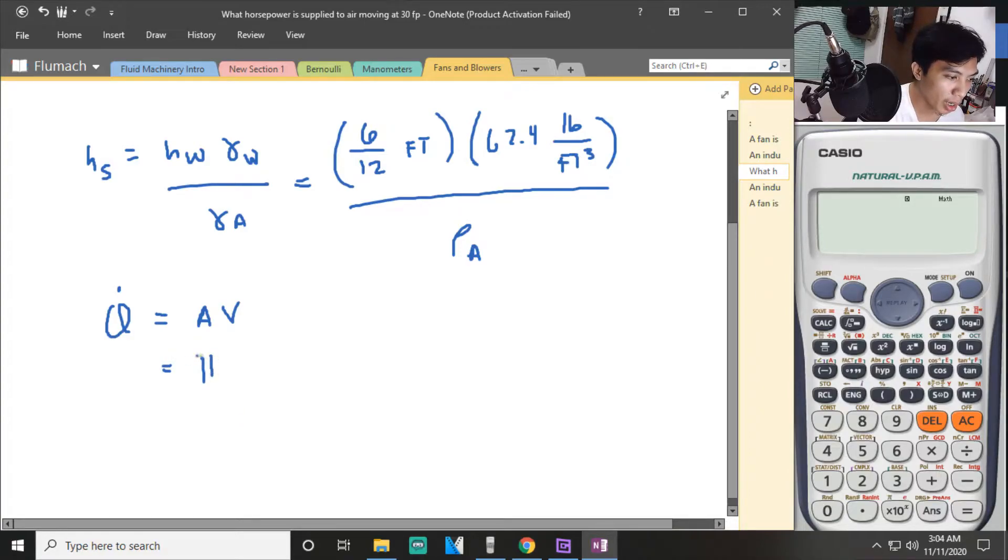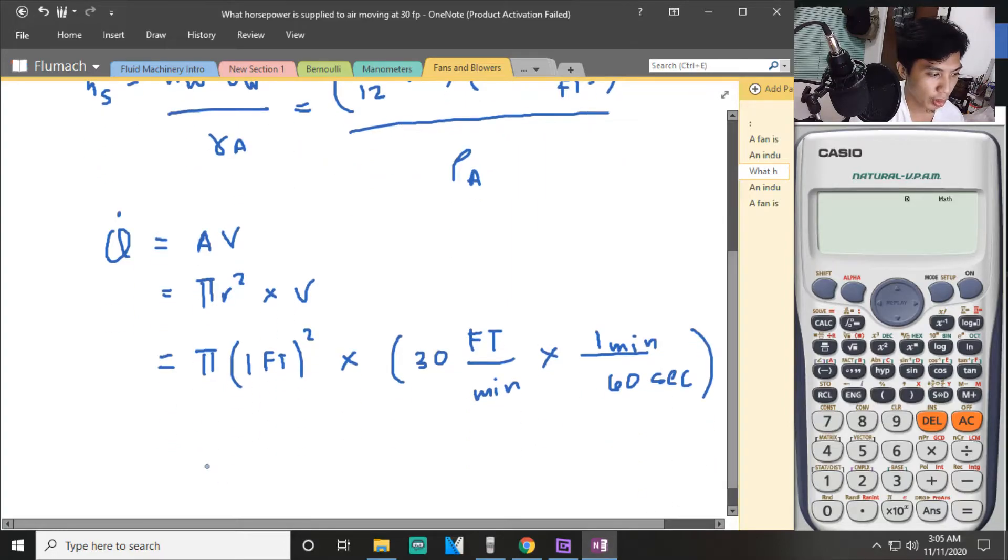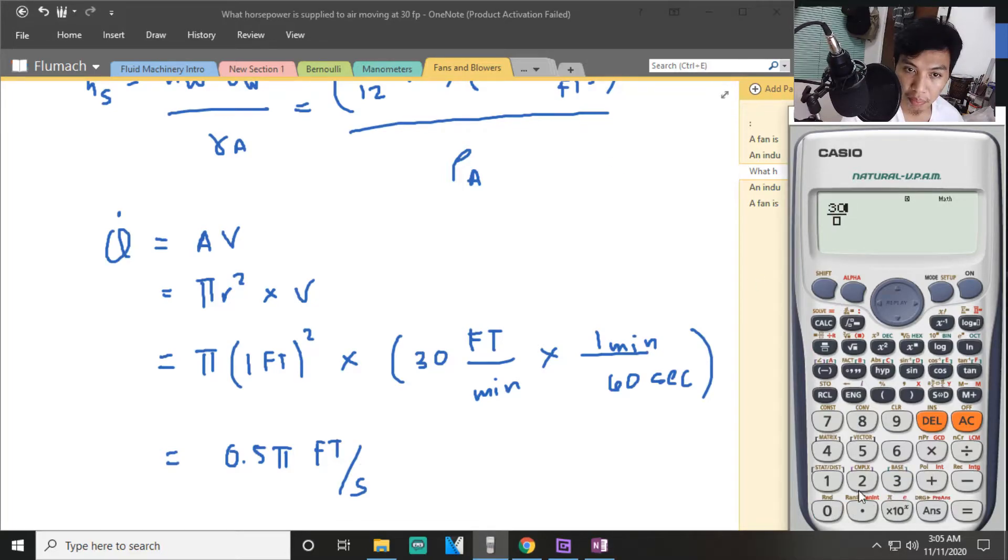Area is pi r squared times velocity. Pi, the r is 1 foot, 1 squared, times the velocity that is 30 feet per minute. Multiply by the conversion unit of minute, 1 minute every 60 seconds. So Q will be pi times 30 divided by 60. So this is 0.5 pi feet per second.